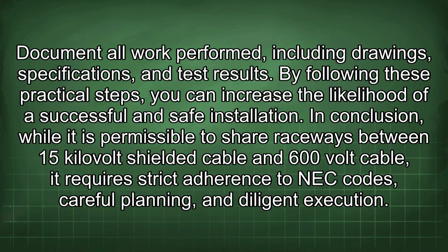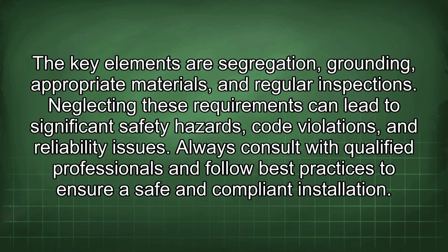In conclusion, while it is permissible to share raceways between 15 kV shielded cable and 600 volt cable, it requires strict adherence to NEC codes, careful planning, and diligent execution. The key elements are segregation, grounding, appropriate materials, and regular inspections. Neglecting these requirements can lead to significant safety hazards, code violations, and reliability issues. Always consult with qualified professionals and follow best practices to ensure a safe and compliant installation.